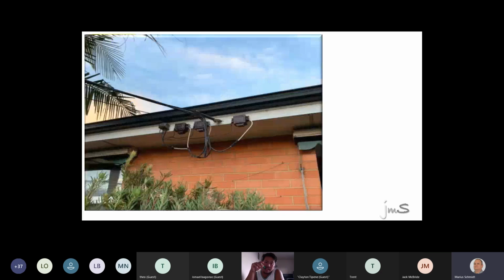What is that? Can you see there are 3 wires coming in? Now, yep, that's a point of entry. My question always is, if 3 wires coming in, red for the stove, red for the hot water cylinder, red for the phase, and a black for the neutral. But can you see the conductors they use is all black in color? How easy it is to swap conductors around? Easy. Right, we're going to check if that polarity is fine.